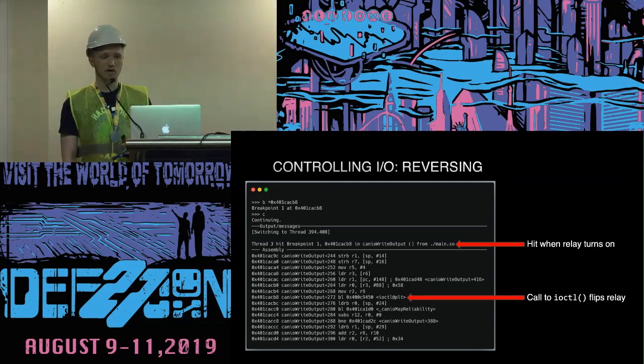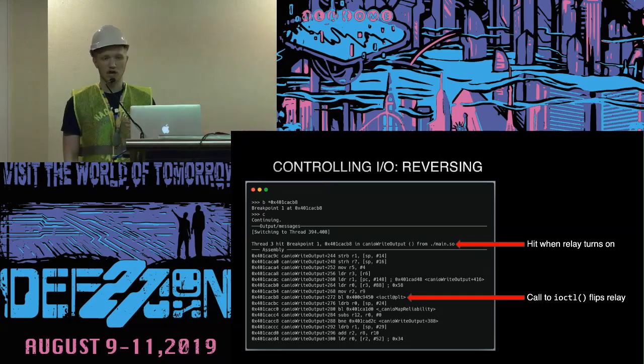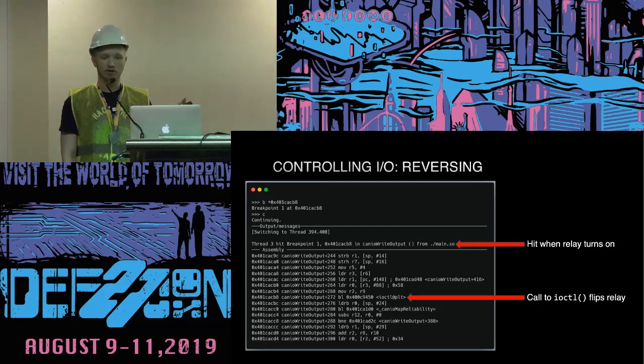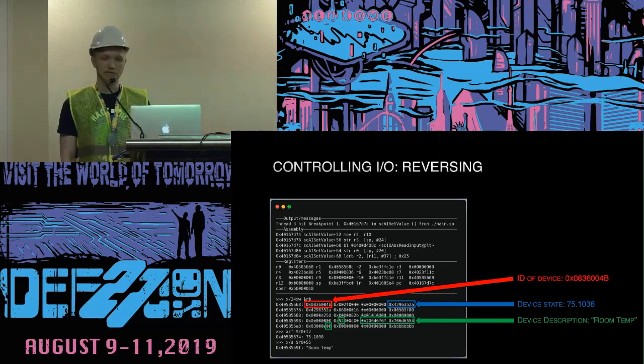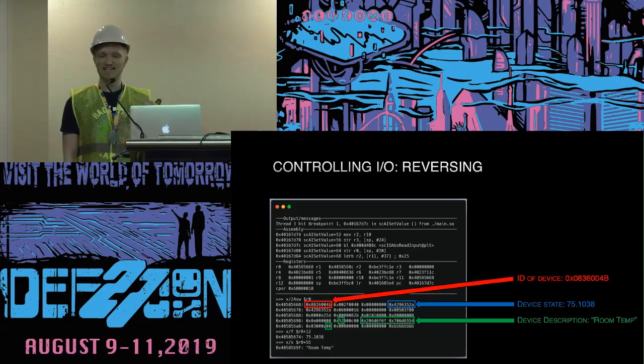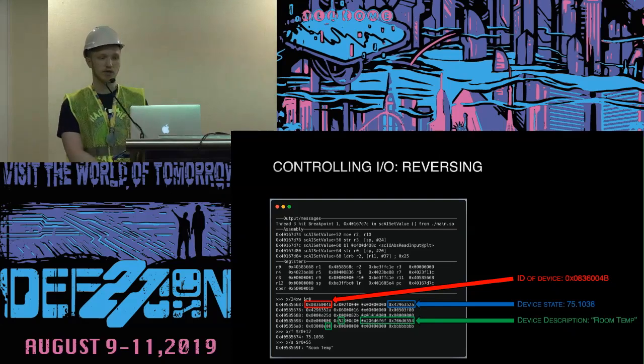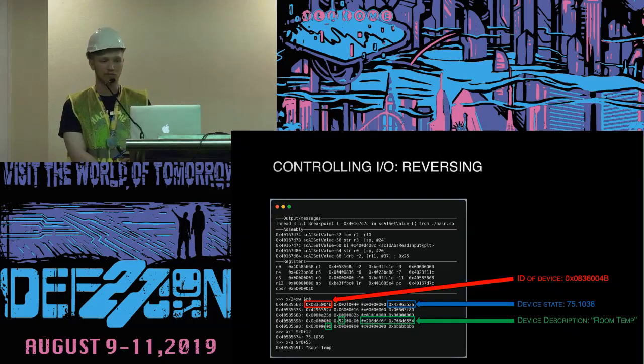Through further reversing of the I/O control functions, we discovered there are different functions for handling all the different categories of I/O — six categories for the eBMGR: inputs, outputs, and variables, each either analog or binary. The idea was to alter the parameters going to these functions. We found one key commonality: the first parameter is a data structure that describes the hardware being altered. The first four bytes are the ID or fingerprint of the device, unique to each one. At a 12-byte offset, we found the current state of the device — the most crucial component. And at a varying offset, a descriptive string identifies the device, which is how we knew one was responsible for monitoring room temperature.